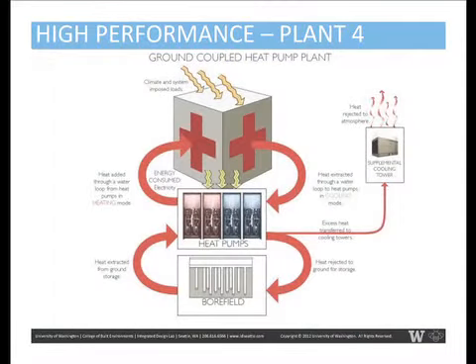This is another important point, I think, is that when there's a choice of like, do we include it or do we not, it's kind of on the borderline. So for example, a supplemental boiler, do we really need it? We put it in because we wanted to err on the side of being conservative. Another example is radiant heating panels at the sidewall in Phoenix and LA. Maybe you don't need it. Maybe a week a year you do. So we put it in for the cost model, so it's represented there.